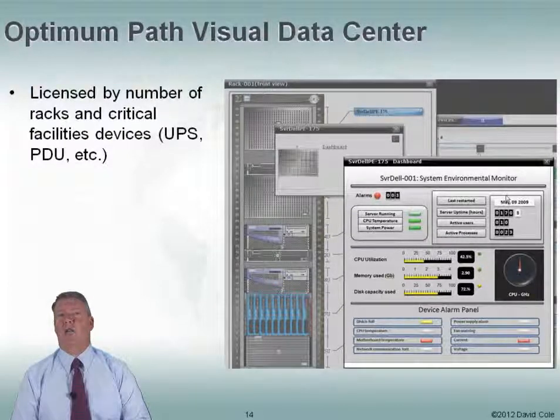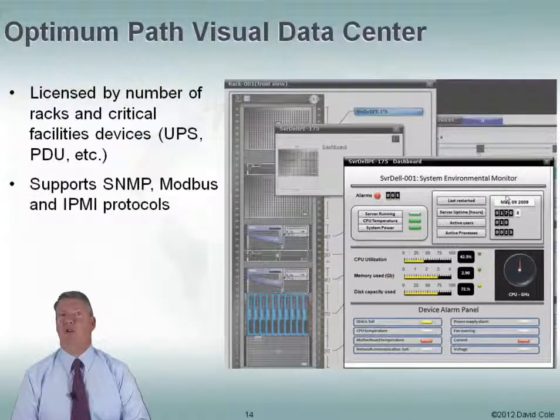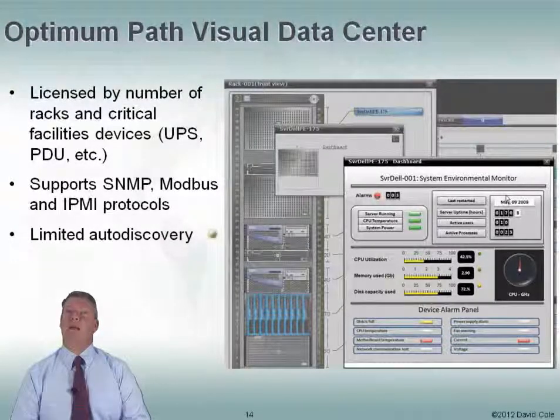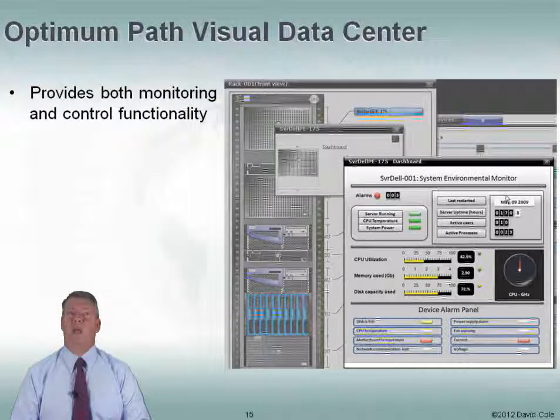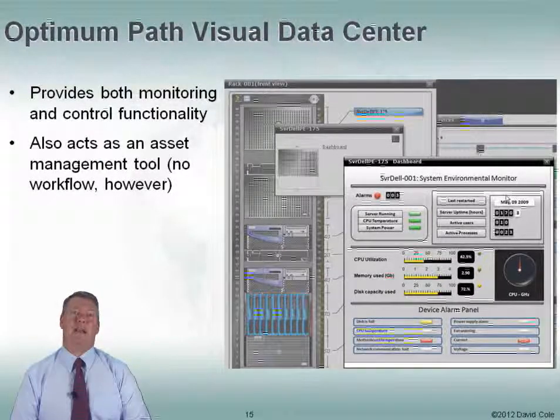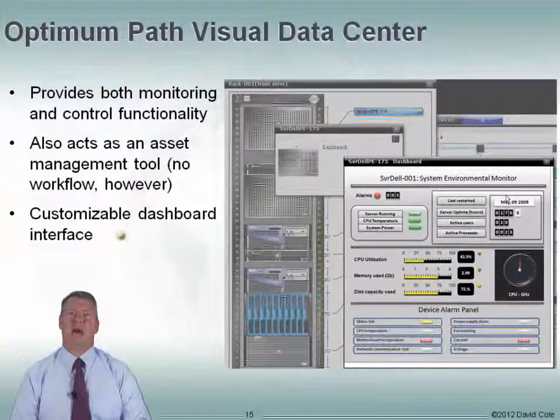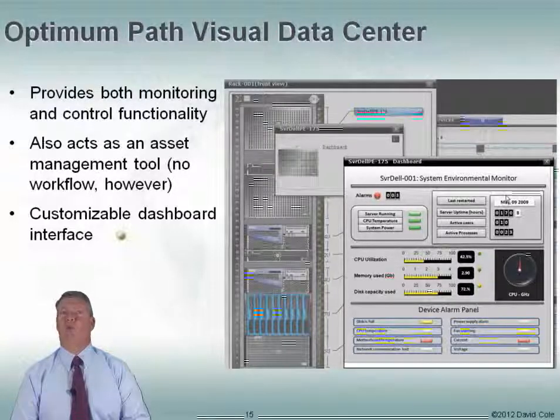Optimum Path Visual Data Center is a nice product. It supports some limited auto discovery. It is licensed by the number of racks and the number of critical facilities devices — UPSs, PDUs, and so on. It supports multiple protocols: SNMP, Modbus, and IPMI. With limited auto discovery, some devices can be discovered automatically, making setup easier. They provide both monitoring and control functionality. It also features a 3D model — you can do a fly-through of the data center. It can also act as an asset management tool, though it doesn't provide workflow. They have a customizable dashboard interface, and a lot of the customization can be done yourself with the tools they provide.